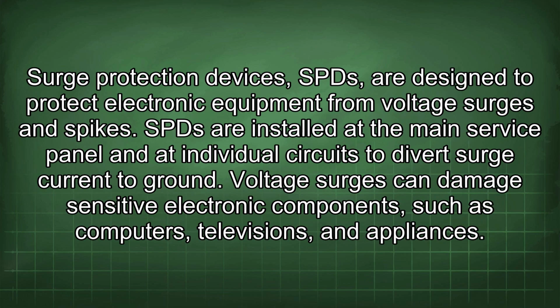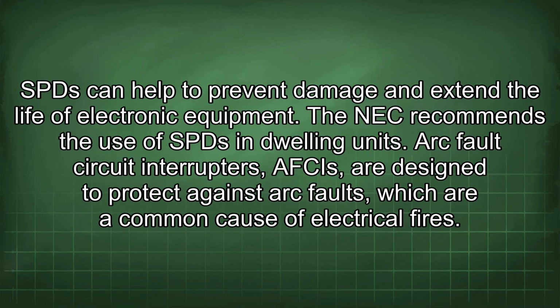Surge protection devices, SPDs, are designed to protect electronic equipment from voltage surges and spikes. SPDs are installed at the main service panel and at individual circuits to divert surge current to ground. Voltage surges can damage sensitive electronic components such as computers, televisions, and appliances. SPDs can help to prevent damage and extend the life of electronic equipment. The NEC recommends the use of SPDs in dwelling units.